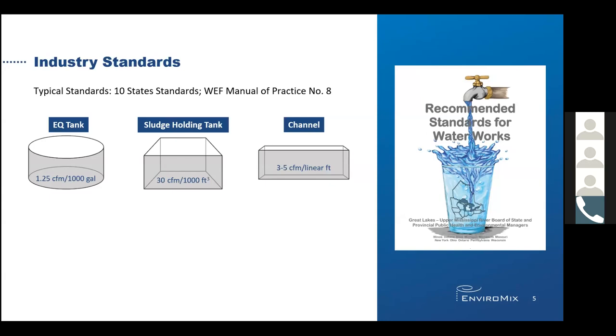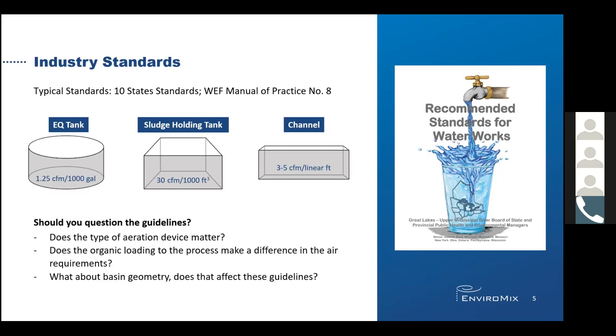For example, take 10 States Standards and MOP-8 recommended guidelines for aerated mixing rates for equalization, sludge holding, and channels. As a designer, one should question these guidelines and ask: does the type of aeration device matter? Does the organic loading to the process make a difference in the air requirement? What about basin geometry? Does that affect these guidelines? We will seek to answer these questions.